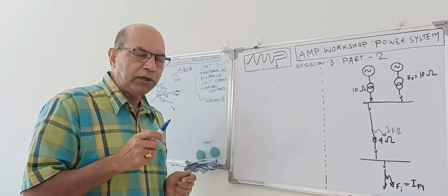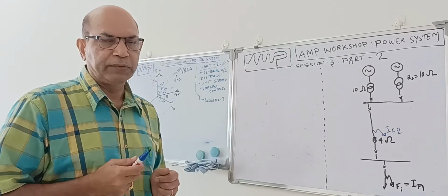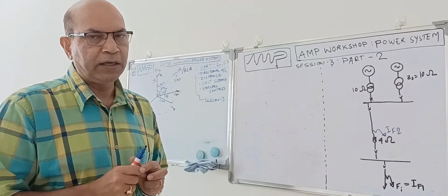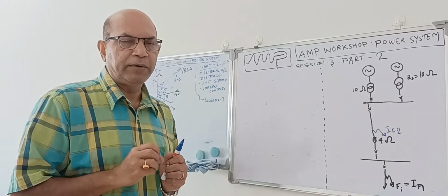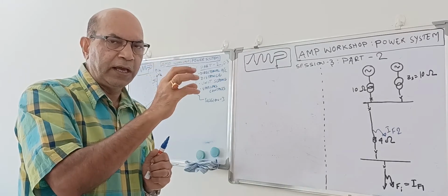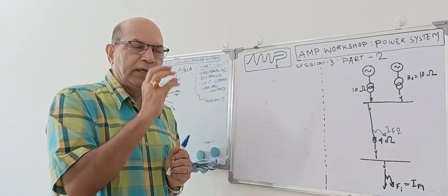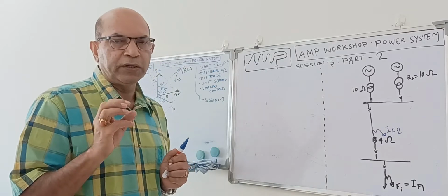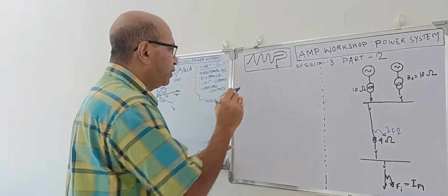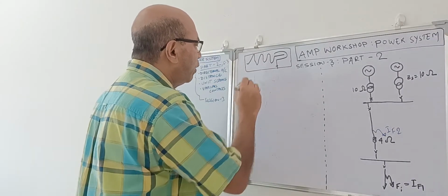And this voltage we always give as a cross reference. Suppose there is a three-phase relay, each phase has one relay element. The relay element which is connected to A phase will get voltage from the other two phases. That is called cross reference. I am drawing a small picture so it will be clear to all of you.